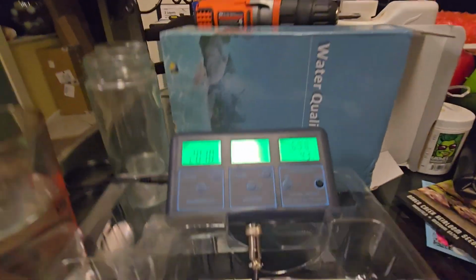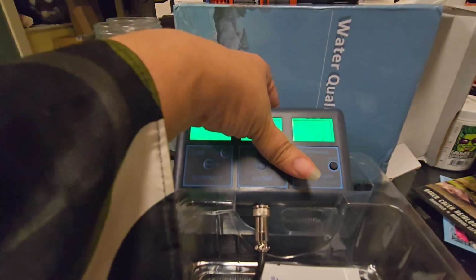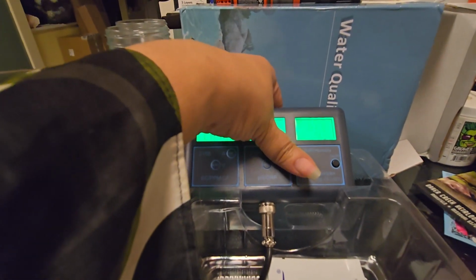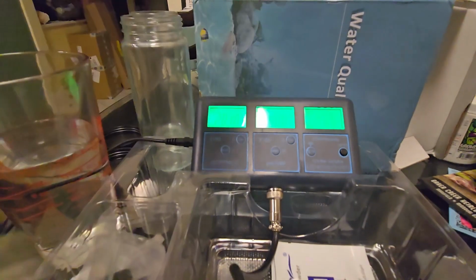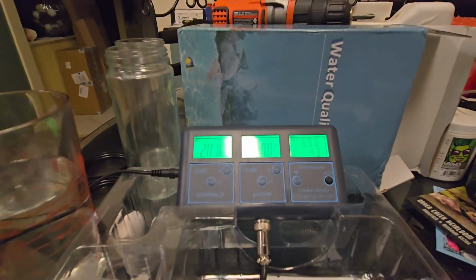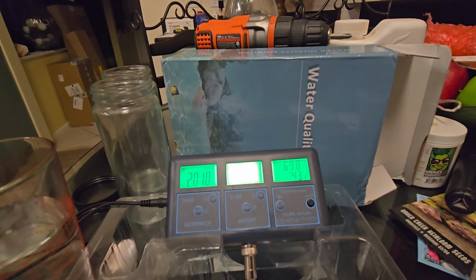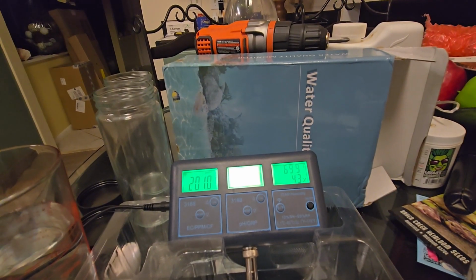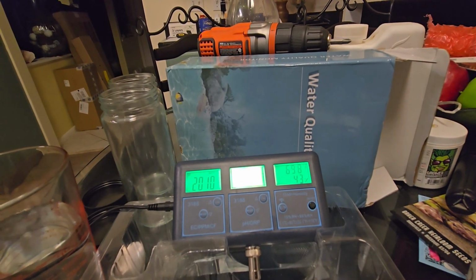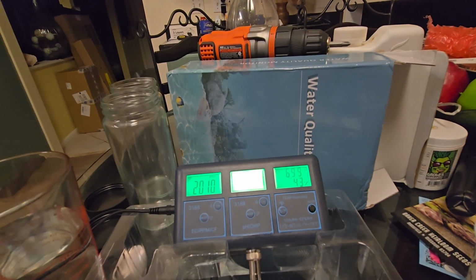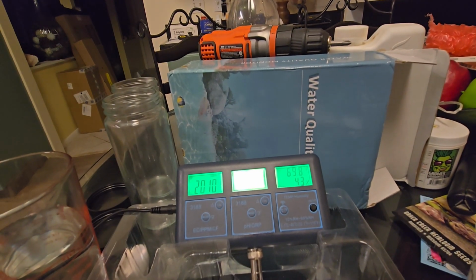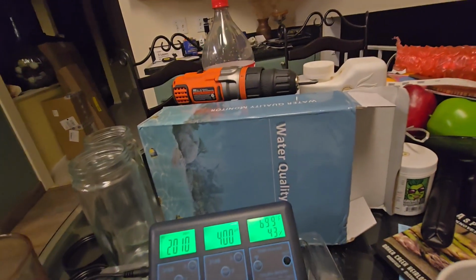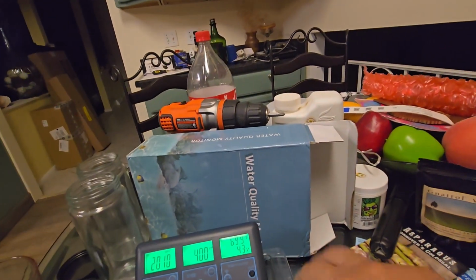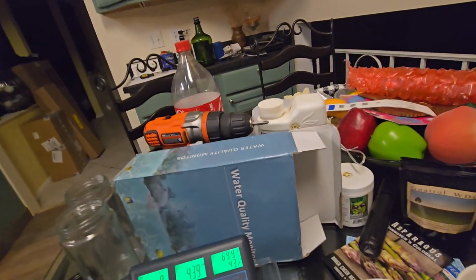Oh, it wanted me to press calibrate for 5 seconds. Let me try that again. 1001, 1002, 1003, 1004, 1005. Okay, it's blinking. It says wait for 4.0 to flash 3 times. Clean the electrode and then try it in the other solution.